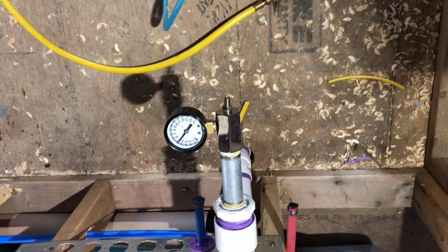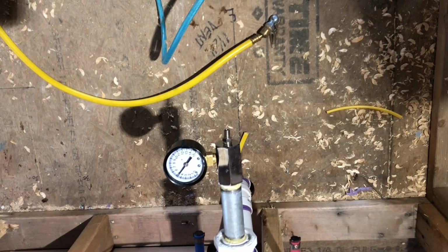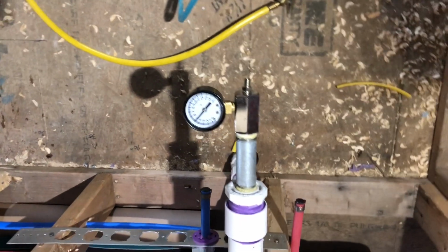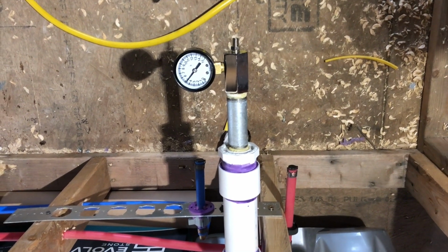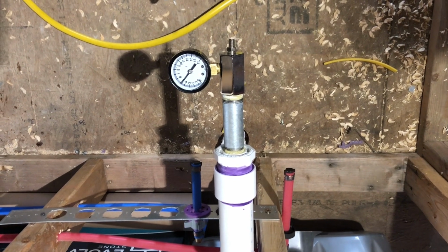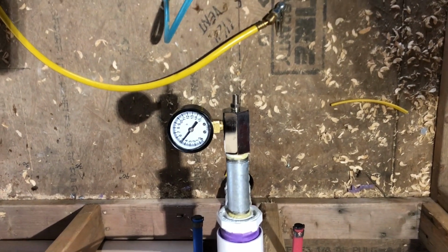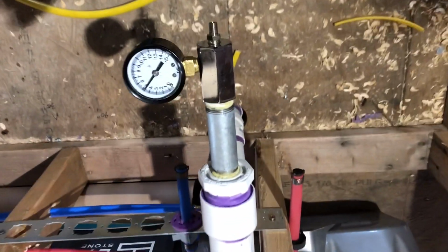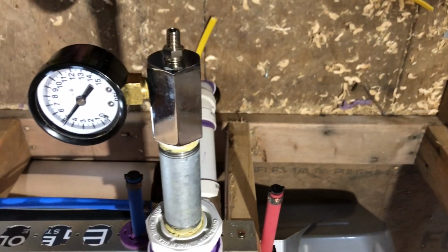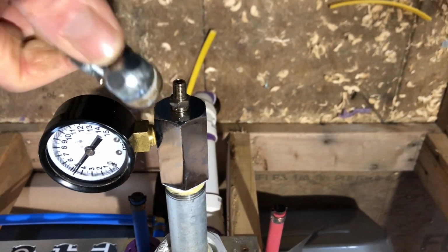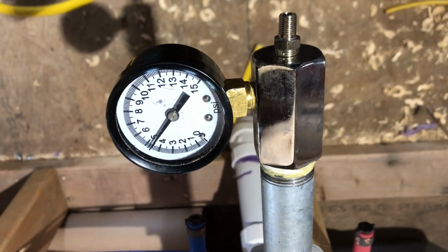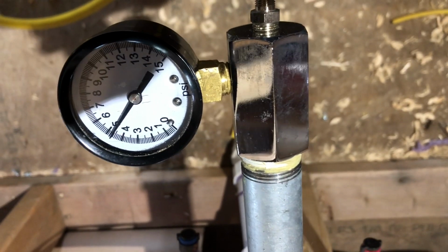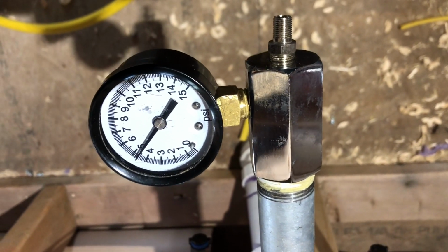The inspector will need to see 5 psi test pressure on our drain vent system. He'll need it to be on there for a 24-hour period without a leak. This is my test setup here. I have a pressure gauge connected to my vanity sink drain line, and I use this air chuck on my air compressor, so I can pump it up to 5 psi and we can watch the test pressure there. So we do have a leak. You see where it's leaked down just a little bit, and we're going to be looking for that in just a minute.